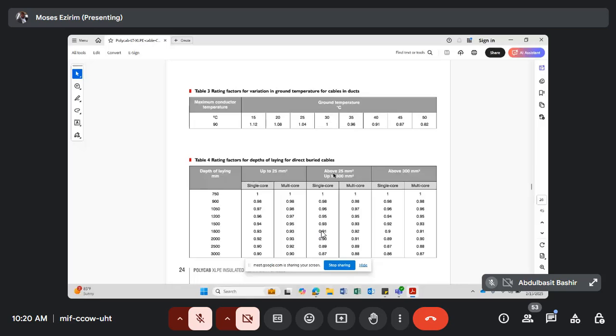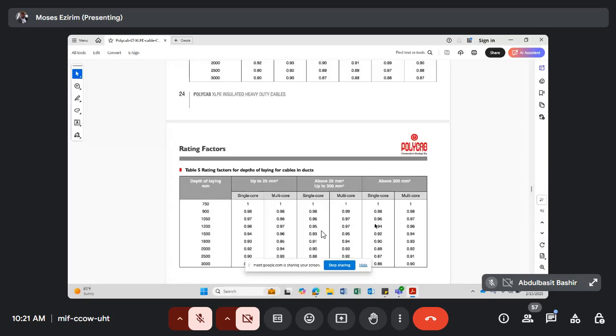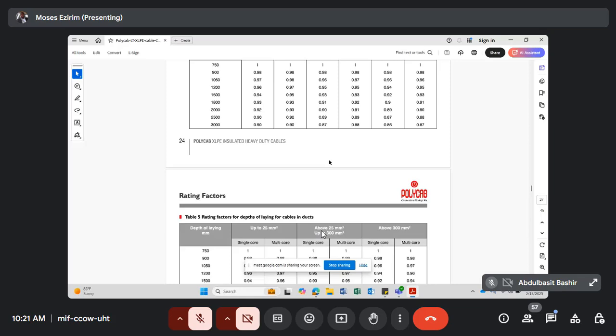But if it is above 25 mm, but up to 300 mm, all right, and I'm going, let's say, 2 meters, which is 2000 mm, then it is multi-core, and I will use 0.91. Can you see it? So my resistance stands, all right, that is the derating factor. But don't worry, go back to my slide. So on my slide now, calculate the overall derating factor.